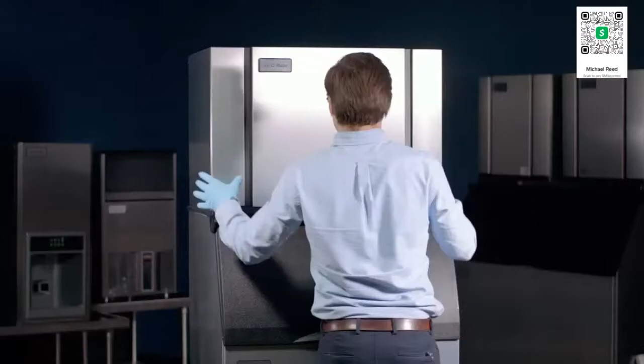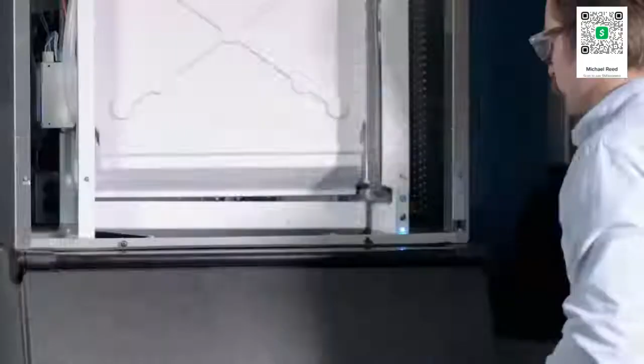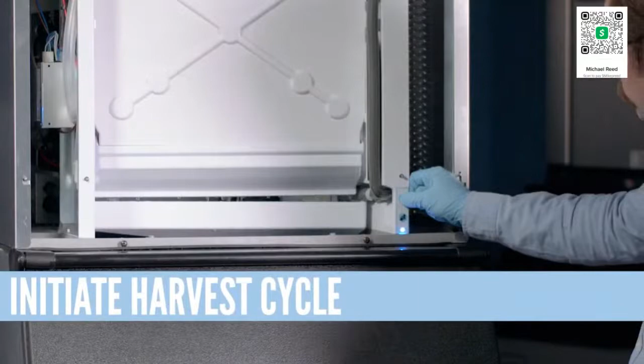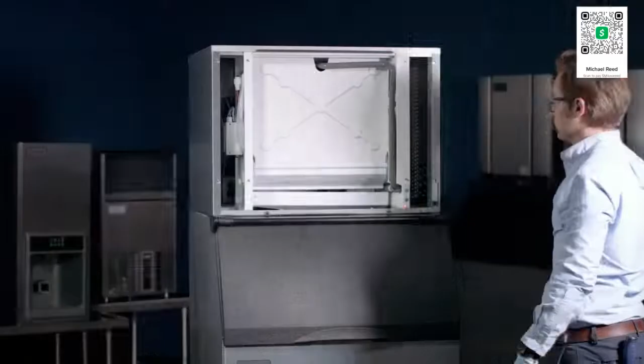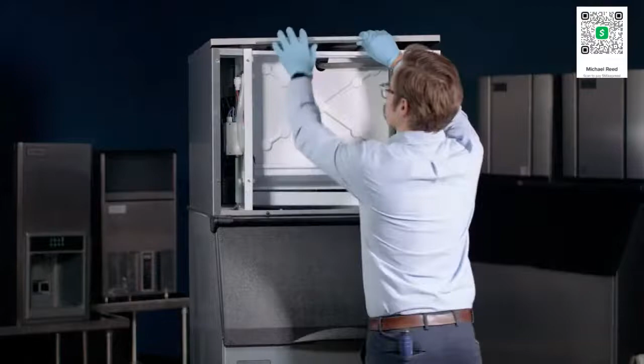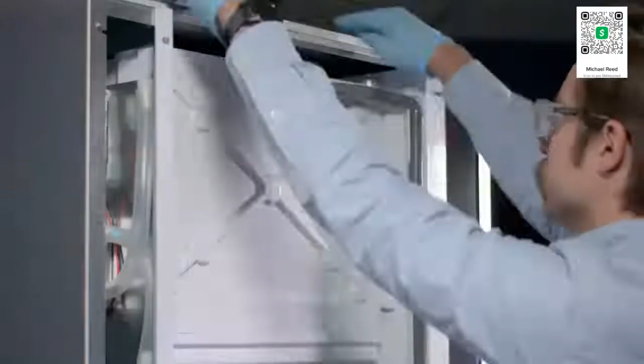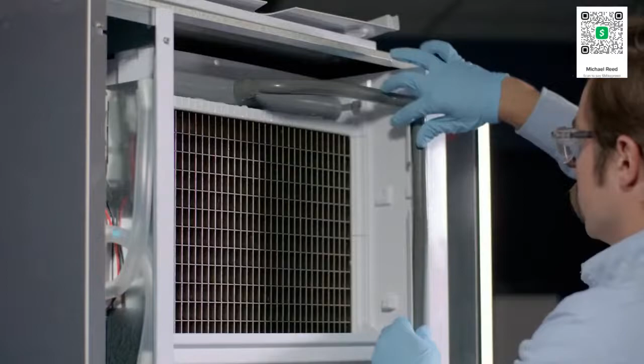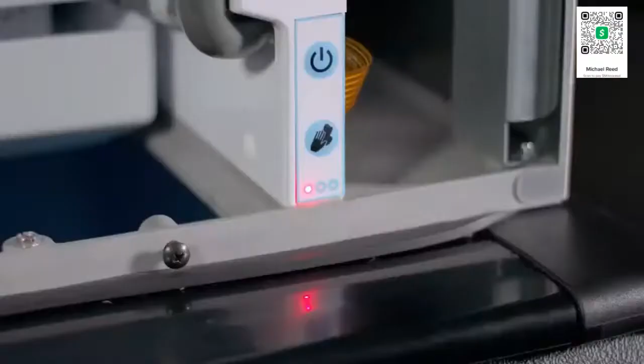The front panel is removed easily with a Phillips head screwdriver. With the front panel removed, hold the power button for 3 seconds to initiate the harvest cycle. With the cycle complete, your machine will turn to off mode. Remove the top cover and splash guard to easily access the curtain and water reservoir. Press the clean button from off mode to begin the clean cycle.